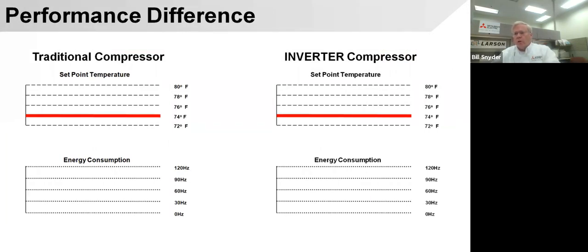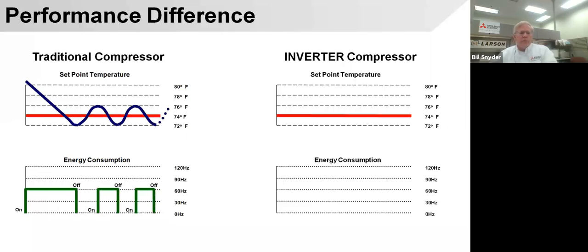A normal compressor just starts and stops. What we're showing here on this chart is kind of a timeline from left to right. If it was 80 degrees in the space and we turned the thermostat on to a set point of 74, the compressor or contactor will pull in and will run for a period of time until the thermostat is satisfied. So we get this type of system with a conventional system where the thermostat comes on, it pulls in the contactor, the ampere on the compressor will typically spike, and we'll continue to run the contactor and compressor until we meet the set point on a conventional thermostat.